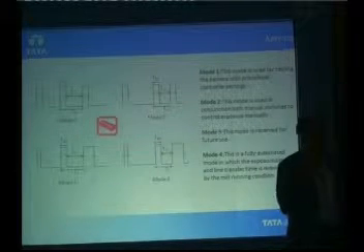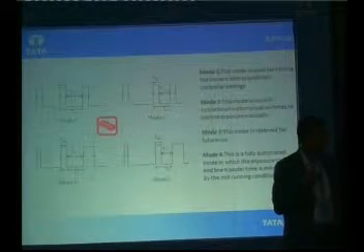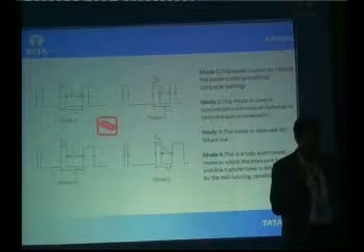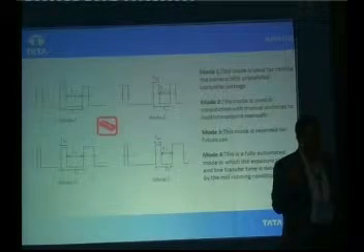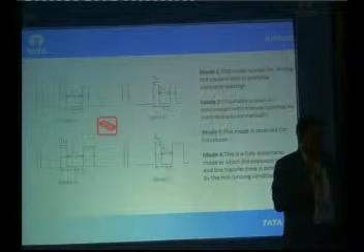Now the mode selection. We have 4 different modes for operating this device. Mode 1 is used for testing, for calibrating the camera against any reference. Mode 2 uses the manual switches I talked about earlier to set a predefined exposure value. Mode 3, we haven't thought of a use yet. And mode 4 is the mode generally used in the plant, where due to varying illumination, or varying intensity or reflectivity of the surface, we can capture constant gray value images.